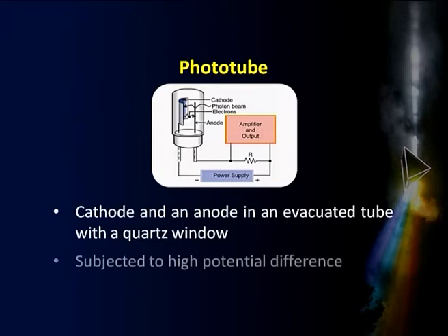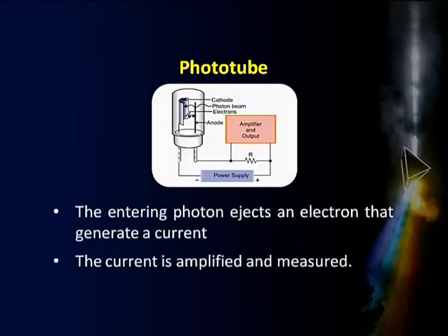And these electrons, because of the potential difference between the two electrodes, are moved towards the anode and generate what is called a current. Okay. So, that is a photoelectric current. The magnitude of this current is proportional to the intensity of radiation falling on it, and that is suitably converted into an output. That means the current which comes as a consequence is measured, amplified, and then suitably converted into an output. So, that is a very simple device.